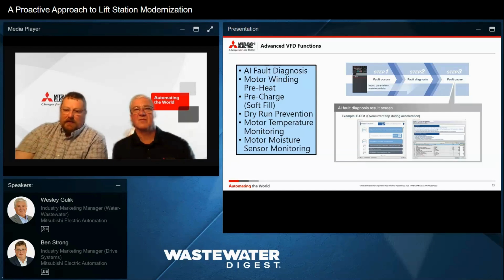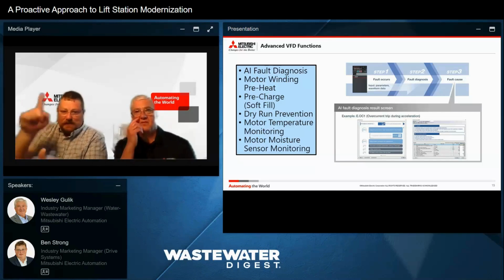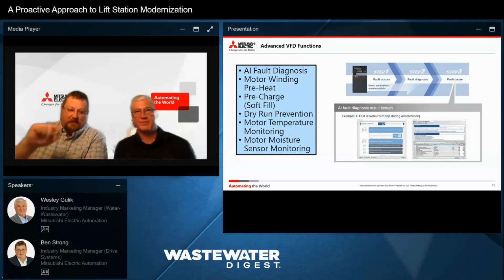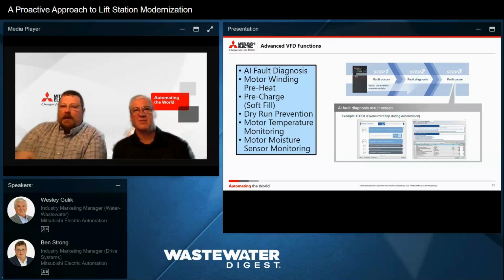So if you're using a drive, a lot of times we have a display where the drive's going to tell us in clear English, I have an overload. Well, if you have a drive with AI on board, then the next thing you may read on that screen is there's an overload condition, and here are the probabilities that this is going to fix it. Normally, we just list them out in the tech manual, and you go 1 through 6 and try to figure it out. If you have some experience, you jump to the one you think it is. If you have the AI, it'll point you to the one it's most likely to be as a corrective action, and I think that's very powerful.